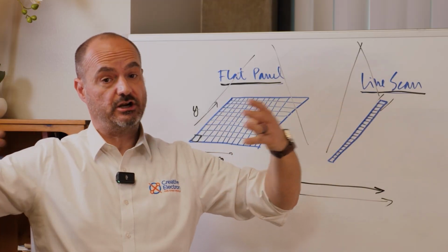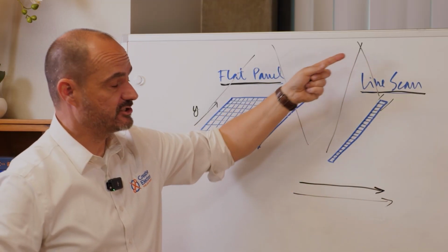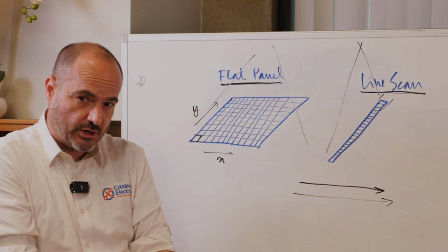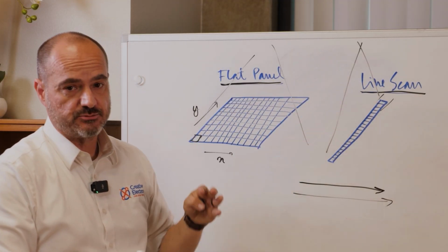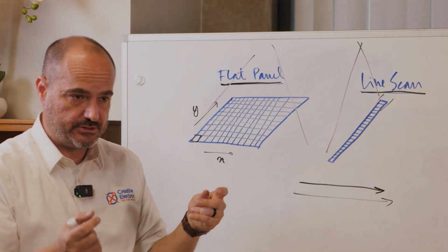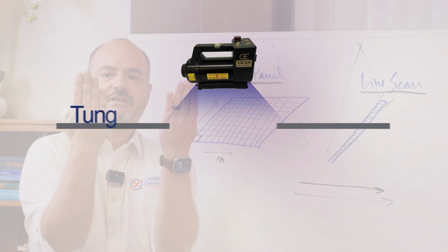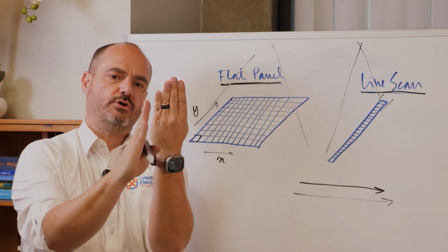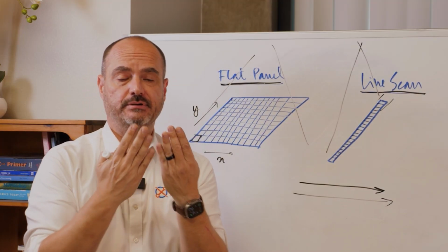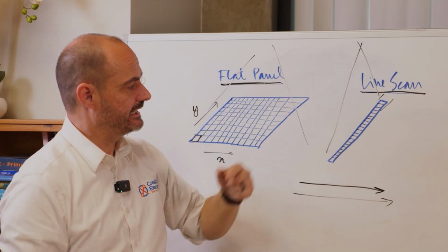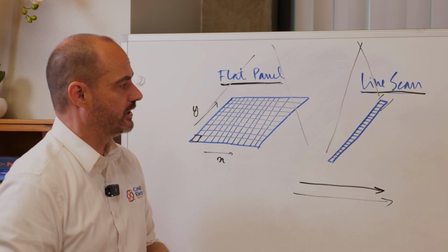Those sides of the machine are open and they're safe because that X-ray beam is really narrow, only on top of the line scanner. And we achieve this by putting in a collimator. Essentially, you have an X-ray source that can be a regular beam, and you put 2 blocks of tungsten or lead with just a little window opening so the X-ray photons only shine through that gap, through that collimator, creating this really nice and sharp X-ray beam for the line scan.